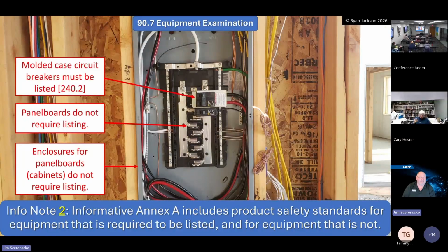And usually a minimum of 10,000 AIC, ampere interrupting capacity, because that's what the breakers are. So every panel board, and again, if you looked at that and said that's a load center, there's no such thing in the code book as a load center. That's just a term we use at the big box store to say I'm buying a load center, which means it's not a bolt-in panel board. It's basically a plug-in style breaker that you put in a residence, which is pretty much all 10,000 AIC, because the available fault currents in most residences are never higher than 10,000 AIC.